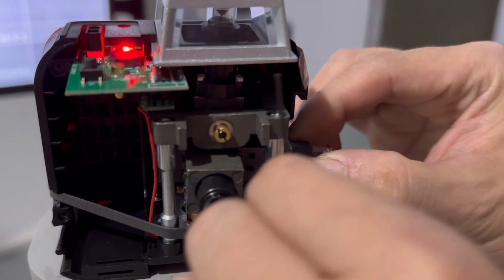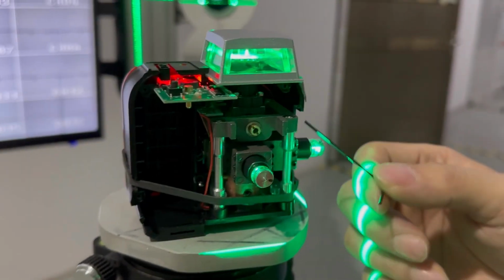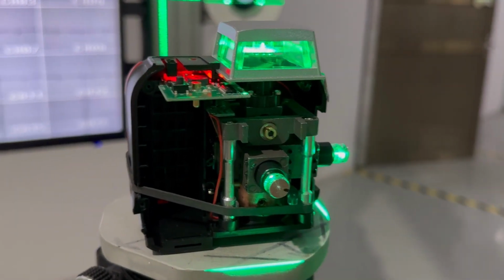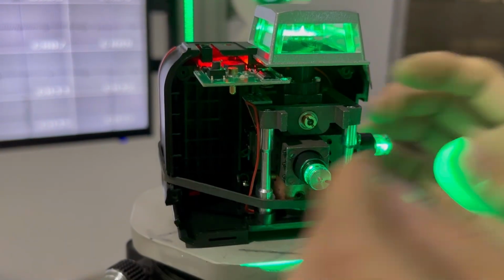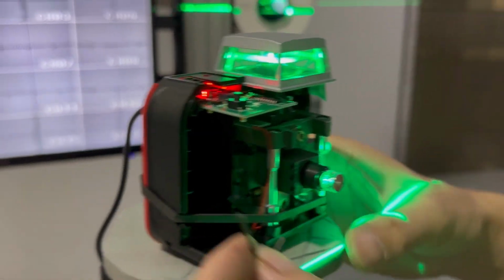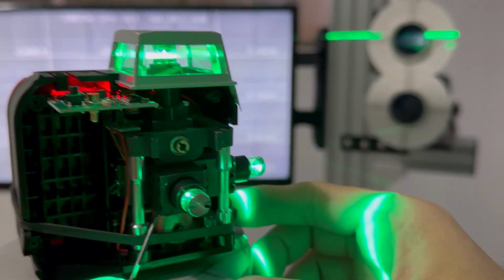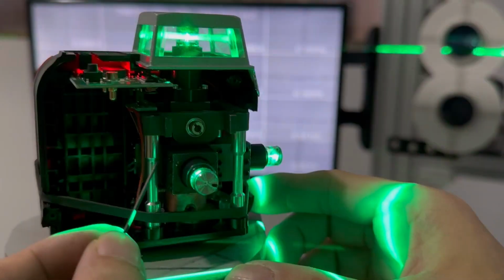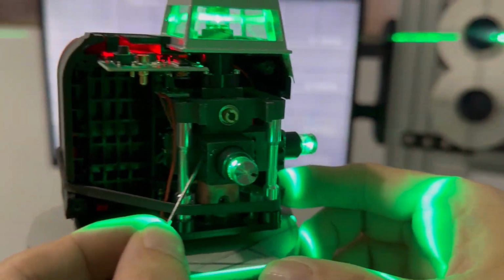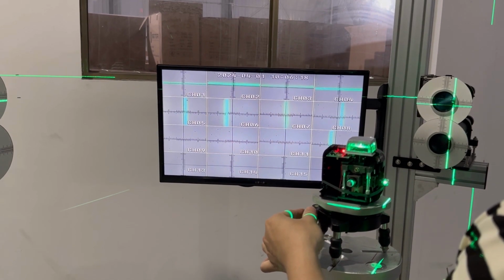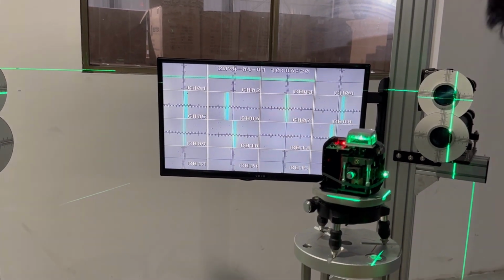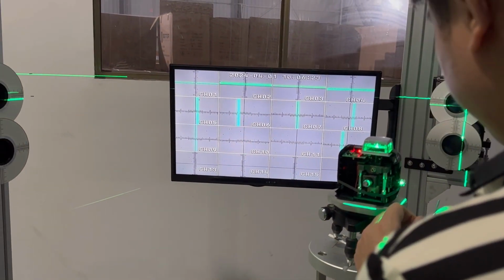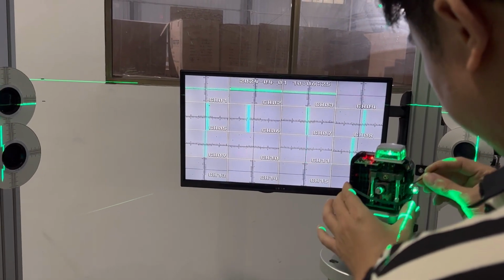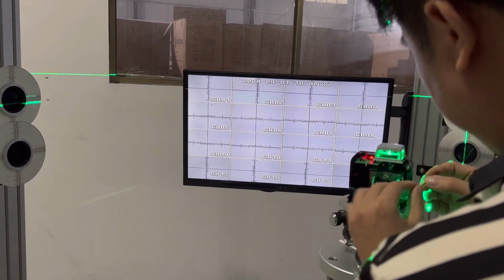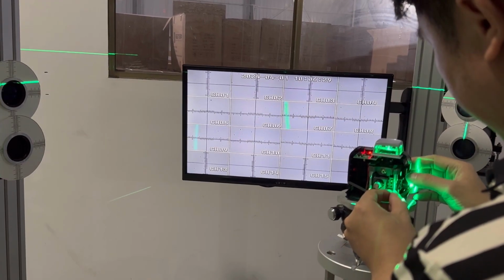Moving to the side vertical dial, also known as the 90-degree beam, the calibration approach remains the same. For this dial, the top and bottom screws are again responsible for adjusting the beam's left and right orientation, while the central screw controls the beam's vertical direction. Let's proceed to the adjustment using the same method to ensure precision in the 90-degree beam's alignment.